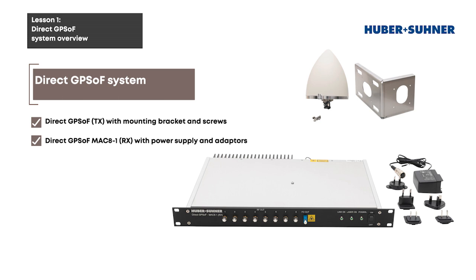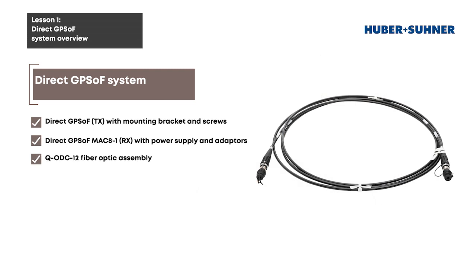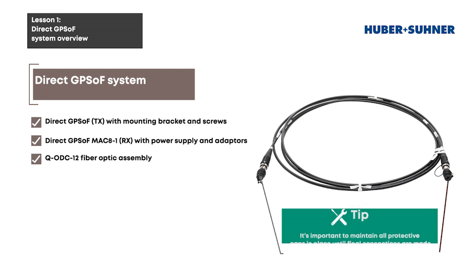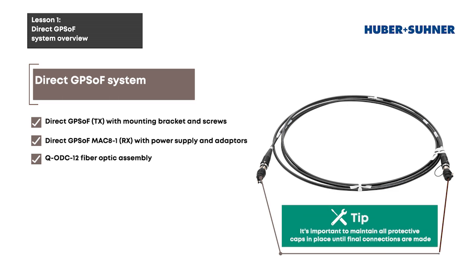An additional item that is not part of the system but needed for installation is the QODC12 assembly or fiber optic cable assembly. All HUBER and SUHNER products are thoroughly cleaned and sanitized in a factory setting. However, dust and debris may settle during transport. A brief inspection with the connector end face quality inspection scope prior to connector mating can save time later in the installation process. If cleaning of the QODC12 connectors is needed, please refer to the troubleshooting lesson of this video.